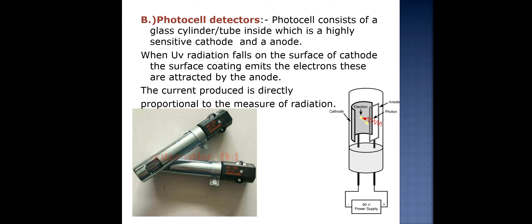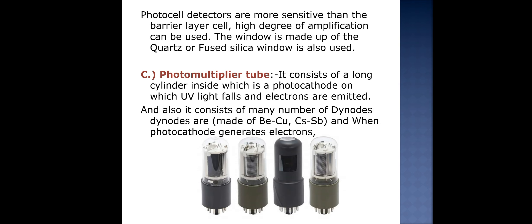The second type of detector is the photocell detector. A photocell consists of a glass cylinder or tube inside which a highly sensitive cathode is placed, with an anode beside it. When light enters the glass and hits the sensitive cathode, electrons are generated from the cathode and move towards the anode, where they are received by the circuit. These electrons are measured, and the current produced is directly proportional to the measure of radiation. Photocell detectors are more sensitive than the barrier layer cell, have a high degree of amplification, and the window is made of quartz or fused silica.